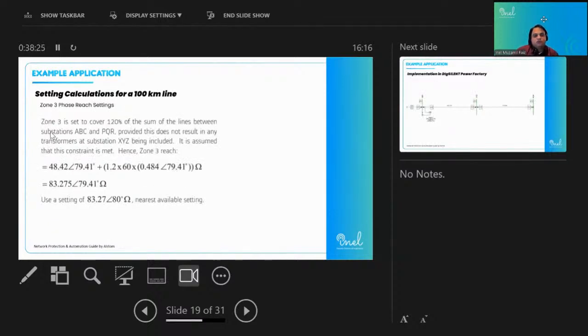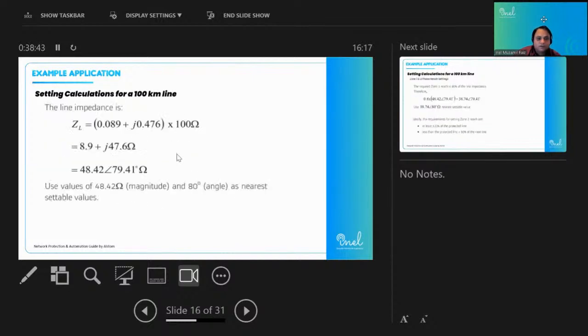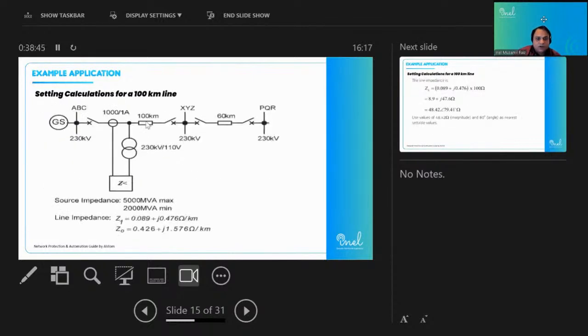And this is the zone 3. There are multiple approaches to calculate zone 3, as with zone 2. One approach is to consider 120% of the sum of the lines between substation ABC and PQR, like this one, 100 kilometer plus 60 kilometer. So the total will be 160 kilometer and 120% of this, so we will multiply 1.2 with that 160 kilometer. This is one approach.